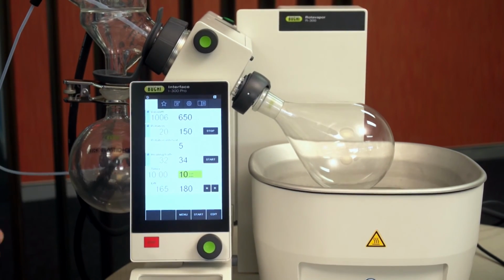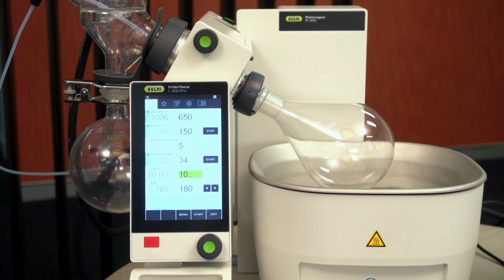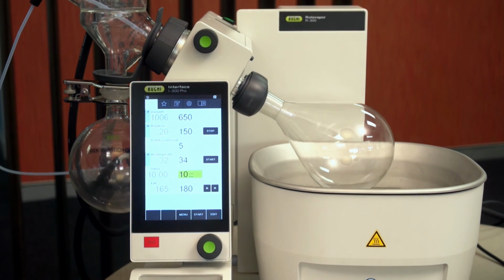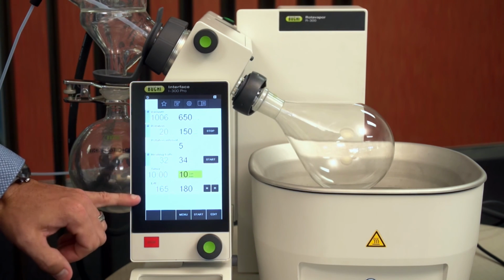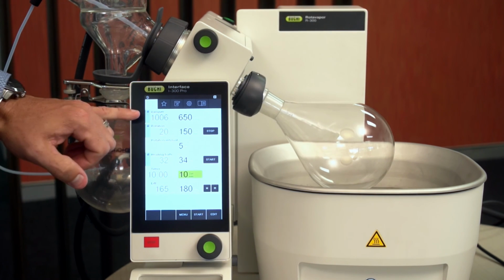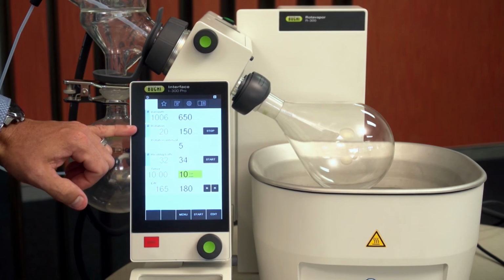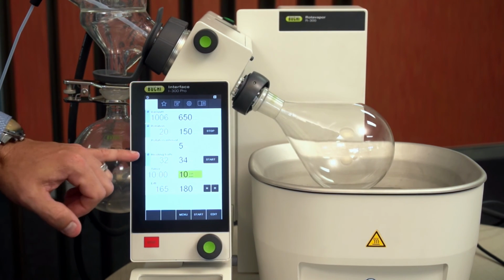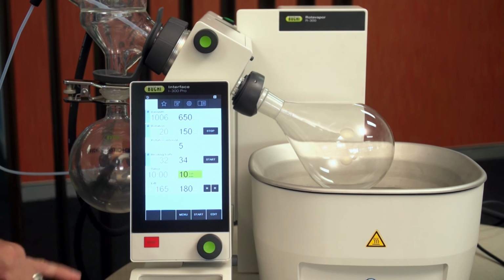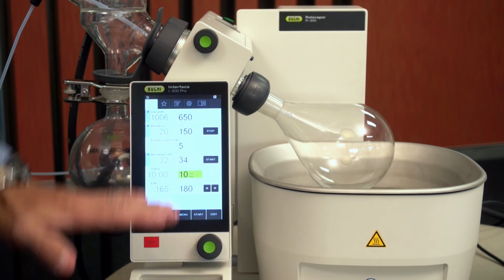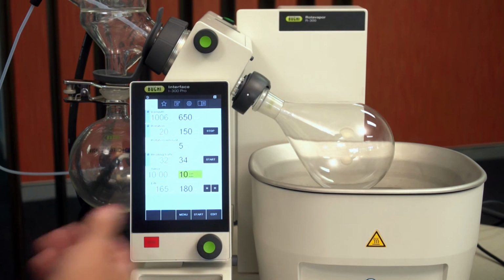If we go into our programming method and we look at dry, so we're going back to the pharmacy lab, going back to a powder or back to somewhere where we have moisture in our sample, we need to get rid of it. You will see we have our set parameters again. We can adjust our vacuum, our rotation interval, and our heating bath temperature, as well as our lift.